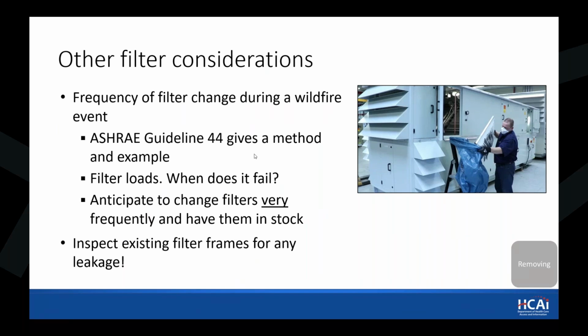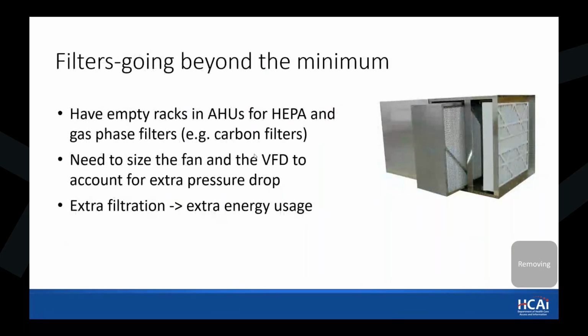Again, one of the other things that we noticed when we were doing some site surveys is that sometimes, instead of upgrading your filter, it's good to check if you have leakage, especially if you have old HVAC systems. Checking your AHUs and all your HVAC equipment, making sure that there is no leakage in the frame is sometimes more important than upgrading your MERV rating. You can always go beyond if you want. And again, as we mentioned, you can go to a higher than MERV 13. You can install HEPA if you want.